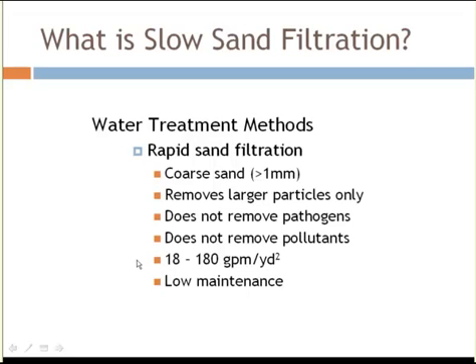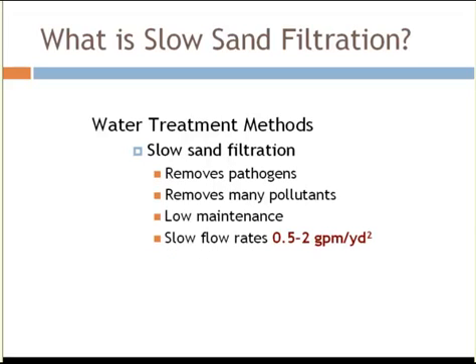The beauty of rapid sand filters, however, is that they have a really high capacity to filter water, they are low maintenance, and this maintenance procedure can be automated. Slow sand filters, on the other hand, are capable of removing pathogens and many pollutants, and they are very low maintenance. The challenge with slow sand filters is that they are slow — treatment rates are typically about a half to two gallons per minute per square yard of surface area of the sand bed.